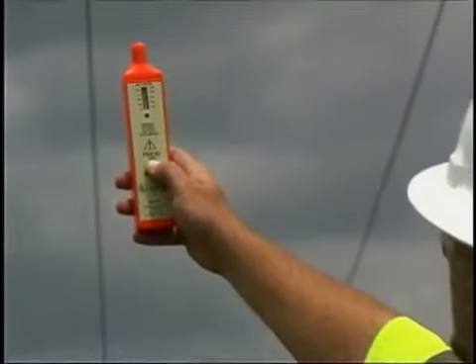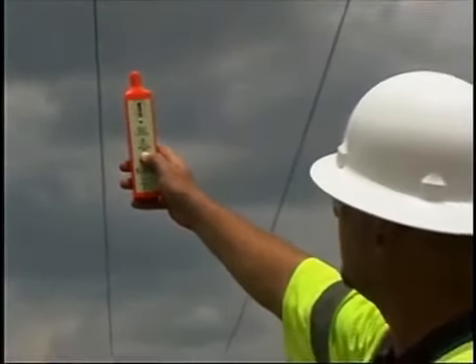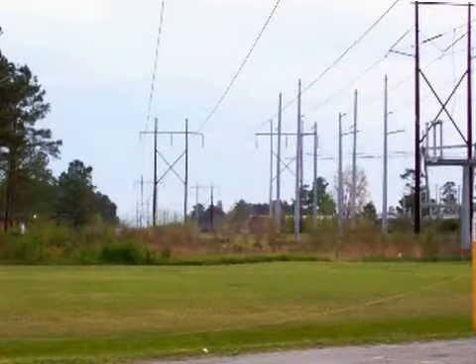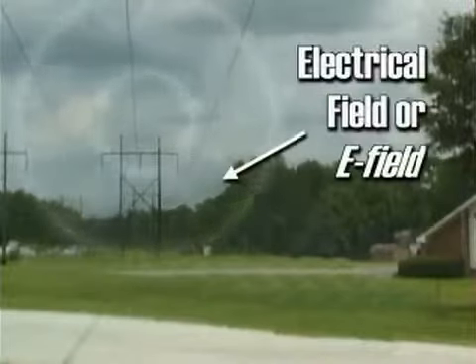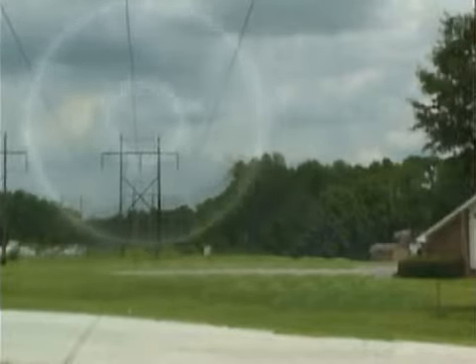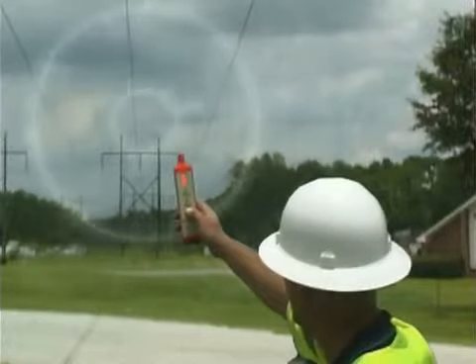This is demonstrated by standing under 230 kilovolt lines with the FVD indicating hazardous voltage. These power lines produce an E field. It surrounds the wires and can encompass large areas. The E field between the power line and nearby conductive objects causes these indications. Ungrounded objects within this E field will accumulate a voltage charge with very little current. The closer the ungrounded objects are located near earth ground, the lower the voltage charge. Because the user of the FVD is within the same E field, he can also become energized. These are not false indications. The indicated voltage does exist on the ungrounded object.